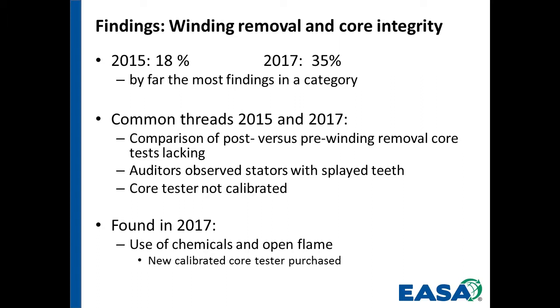Post versus pre-winding removal core test: lacking. What it really came down to is that a lot of service centers are used to doing the post burn-off process core test. But what the program also requires is to do that core test before the winding removal, so that we can compare the after to the before to prove that we haven't increased the losses to a measurable or significant amount. And auditors also observe things like stators with splayed teeth, which I think has been starting to diminish.